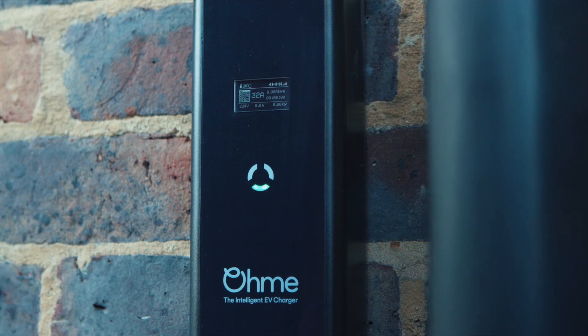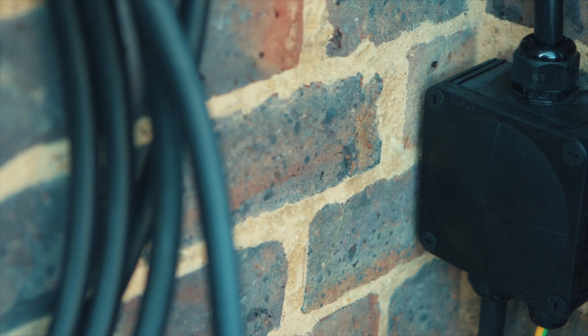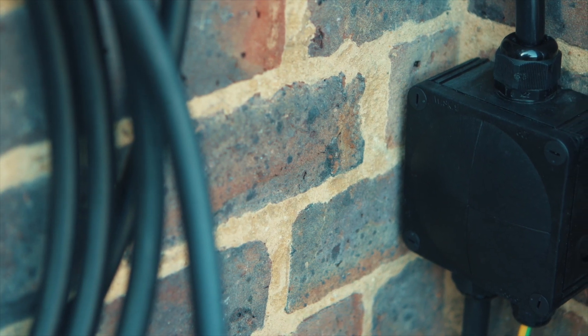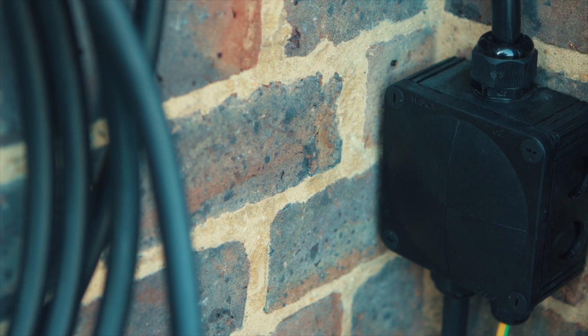For installation, all Ohme chargers come with a flying lead on the input, so this needs to be terminated into a junction box or isolation switch locally. The length of the input lead is 1 metre. The connections to the unit are simply live, earth, and neutral, but bear in mind as per the wiring regulations the earth does need to be TT, which usually means installing an earth rod.